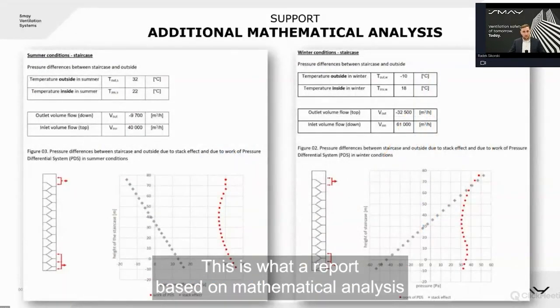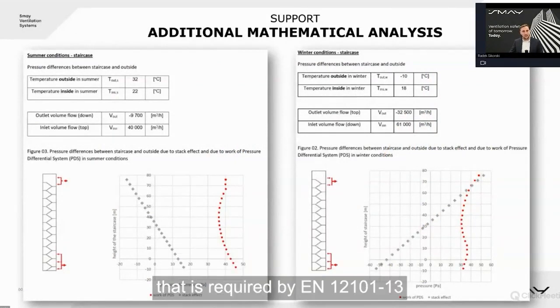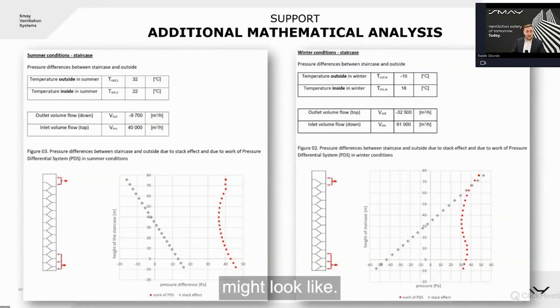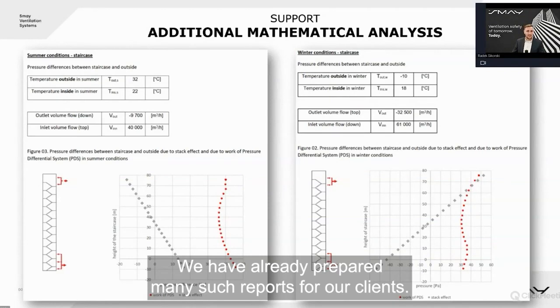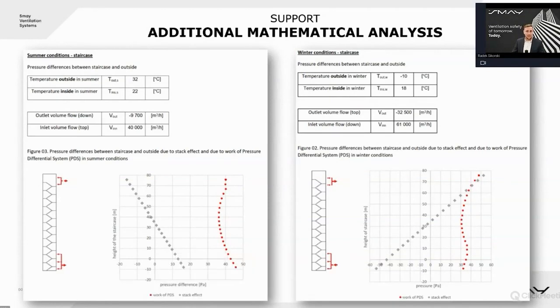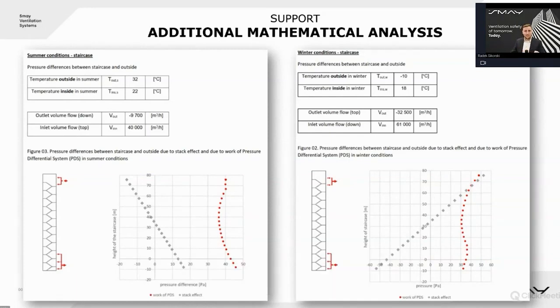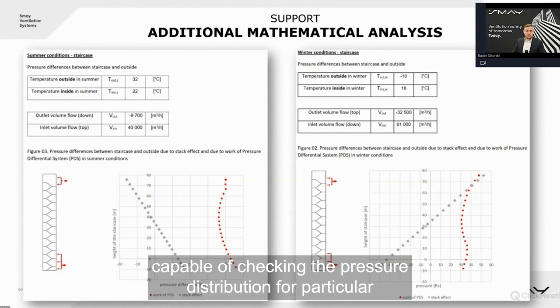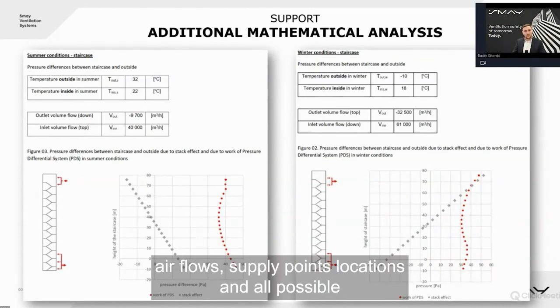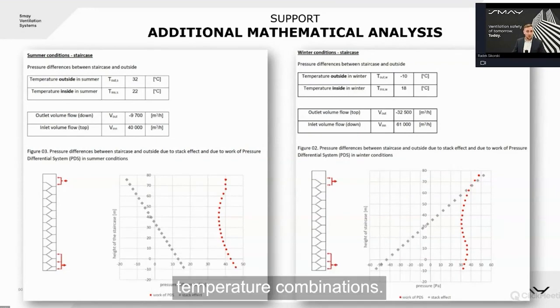This is what a report based on mathematical analysis, as required by EN 12101 Part 13, might look like. We have already prepared many such reports for our clients. The report must include a check of winter, isothermal, and summer conditions. We are capable of checking pressure distribution for particular air flows, supply point locations, and all possible temperature combinations.